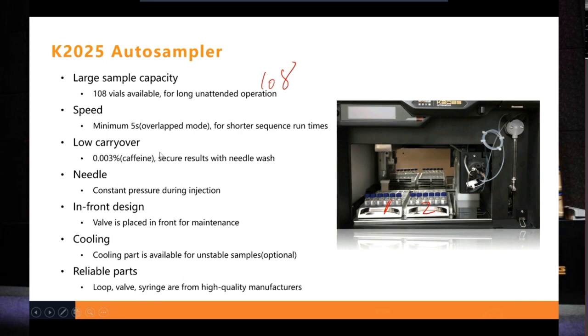Another very important feature for the autosampler is the carryover. The carryover means the sample residue in the autosampler from the last injection that can affect the results of the next round. So the lower the carryover, the better for the next results. And the carryover is less than 0.003%. It is measured by the caffeine.